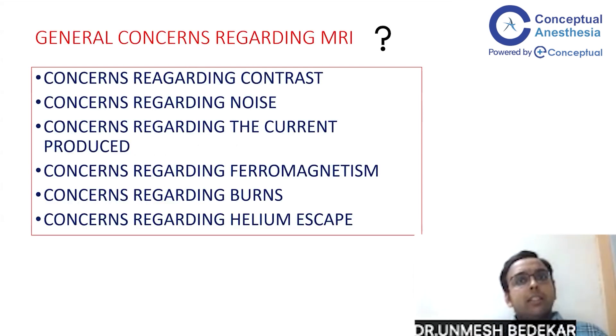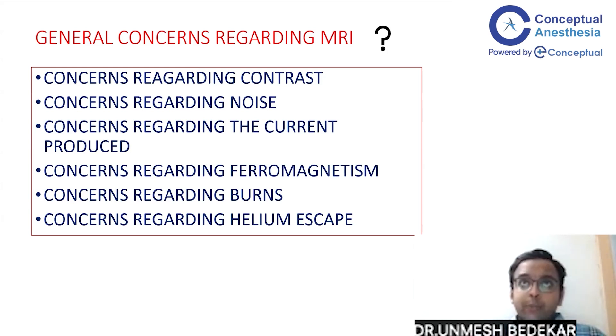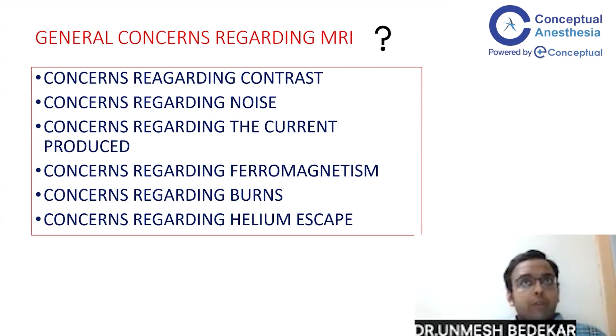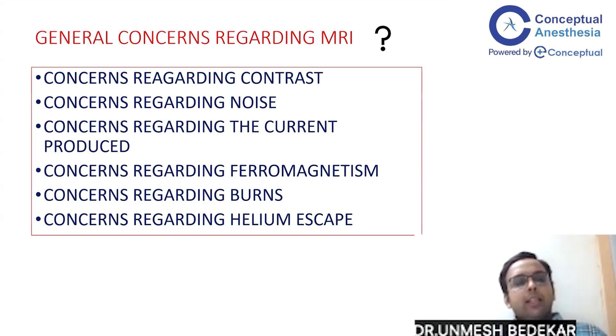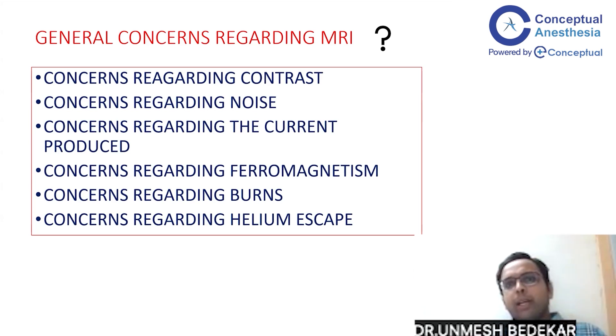The general concerns regarding MRI can be broadly classified into: concerns regarding contrast, concerns regarding the noise produced by the MR scanner, concerns regarding induced current, and concerns regarding ferromagnetism — one of the most important concerns, which has led to patient deaths when ferromagnetic substances were not screened and brought into Zone 4, causing trolleys or patients to be drawn to the magnet. There are also concerns regarding burns and helium escapes.